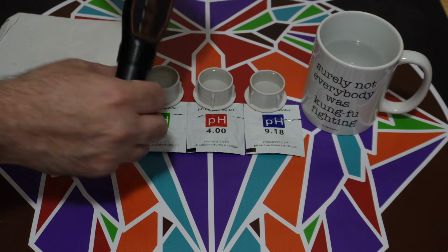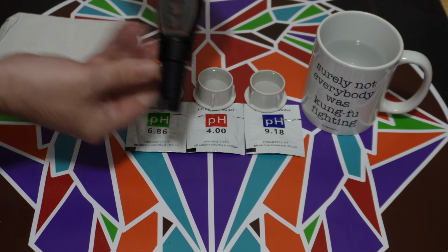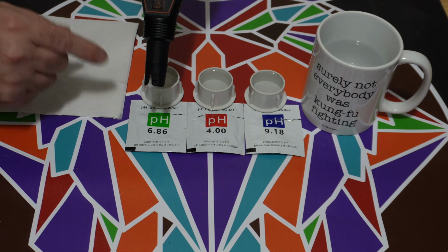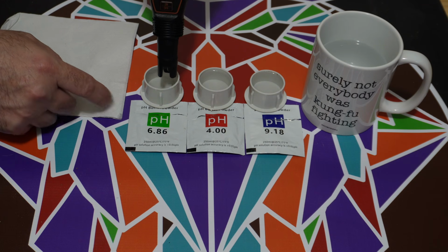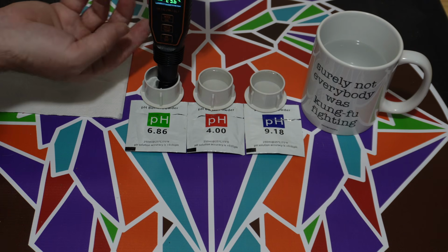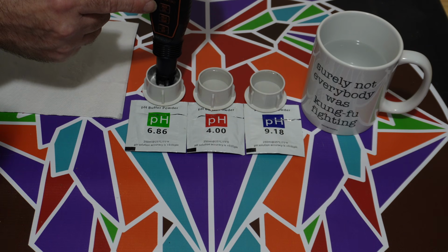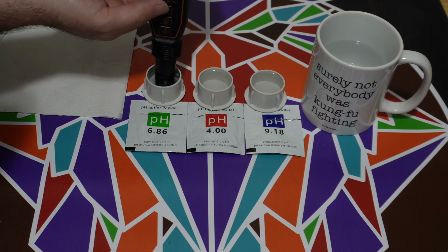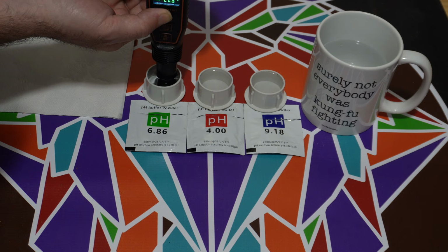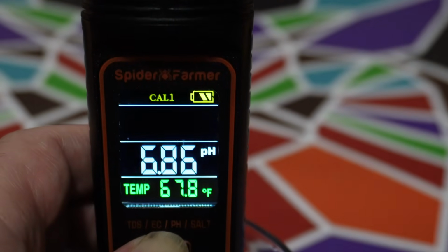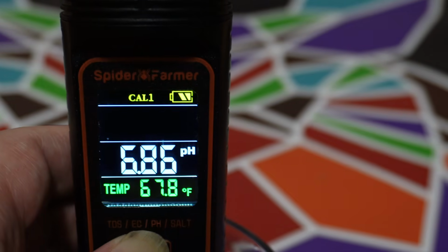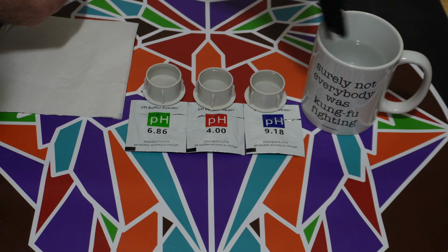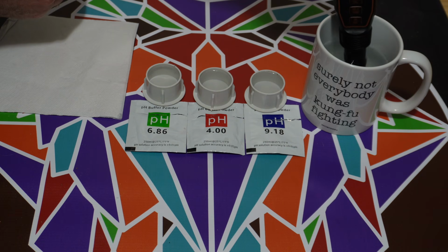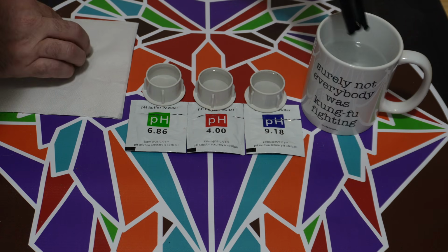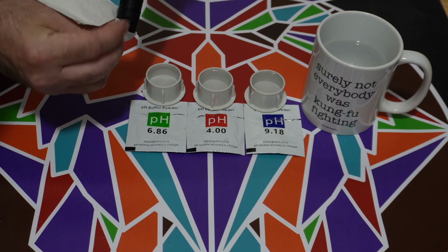So, all right, first thing we got to do, we got to take our cap off so we can get to the probe part of it here. We're going to turn it on. And first thing is we go into the 6.86 solution. It is nice and submerged, and what we're going to do is hold down this button up here, the mode calibrate. We're just going to press and hold that in until it flashes 6.86. There we go, it's flashing 6.86. We're going to let that go. We are then going to rinse it off. And then we're going to dry the glass probe and repeat.